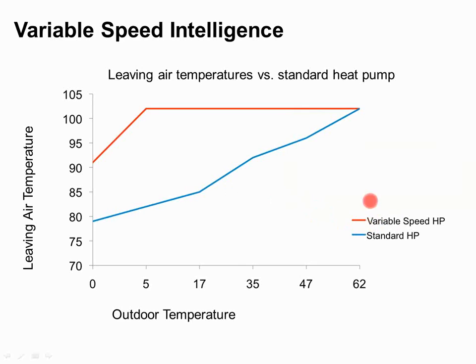If I have a variable speed heat pump, that's the one in red, I'm able to maintain the same discharge air temperature all the way through. What I start doing is slowing down the indoor blower to make sure my discharge air stays higher. Less CFM going across the same amount of refrigerant moving through the coil is going to give me a higher discharge air. So I slow down the indoor blower to keep the discharge air temperature up. Now eventually I'm going to slow down that blower to a point where I can't get the amount of BTUs that I want. So then I have to start speeding that blower back up.